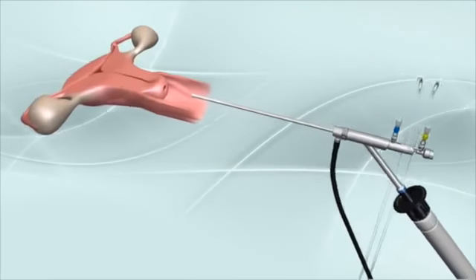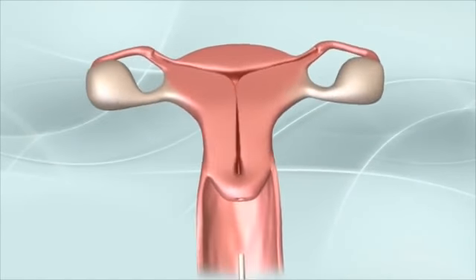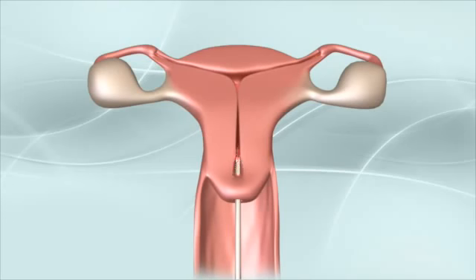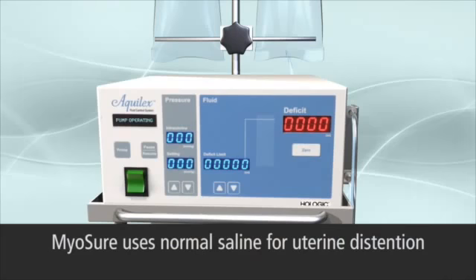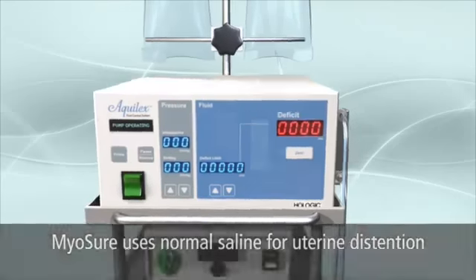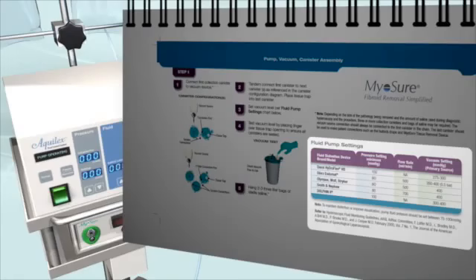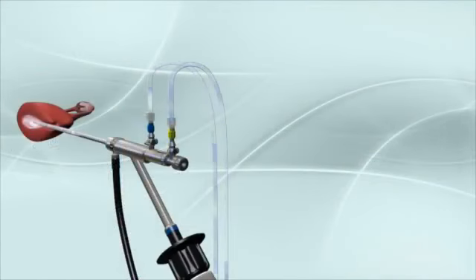The Myosure system enables simple and efficient hysteroscopic removal of tissue. To achieve and maintain uterine distension and optimal visualization while rapidly cutting and removing tissue, it is important to understand the unique fluid characteristics of the Myosure procedure. Inflow of normal saline is achieved by a fluid pump that provides adjustable fluid pressure. It is important to properly set the fluid pump pressure and inflow rates based on the recommendations in the Myosure Setup Guide. The Myosure outflow channel provides continuous flow during the diagnostic procedure and is removed once pathology is confirmed.